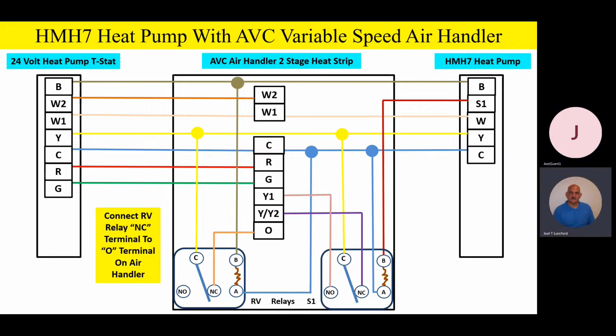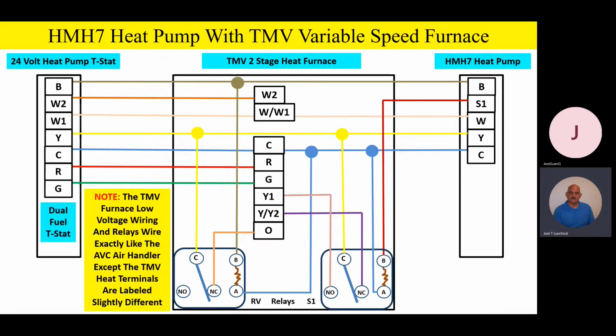Okay, so that's our basic logic right there, that RV relay. The only reason it's there is to break that O terminal in the heating mode of operation. As we jump into our TMV two-stage furnace, it's going to wire exactly like the air handler, except on the TMV furnace the heating terminals are labeled slightly differently. So instead of having W1, W2, we're going to have a W/W1 and a W2 terminal. But other than that, it wires exactly like the air handler as far as the terminals, the Y1, Y2, O terminal, etc. So that makes it pretty simple for a two-stage variable speed furnace. Any questions or comments before we do some animations for everybody? Everybody good?